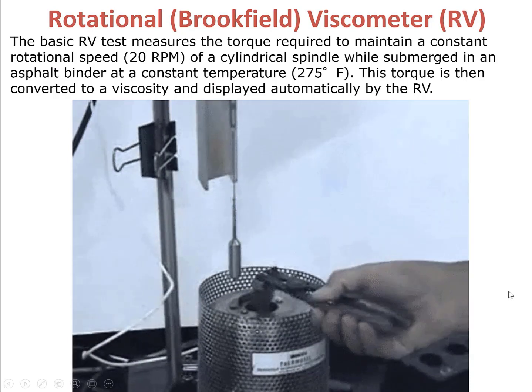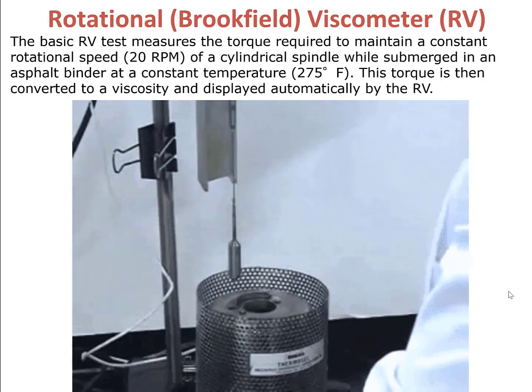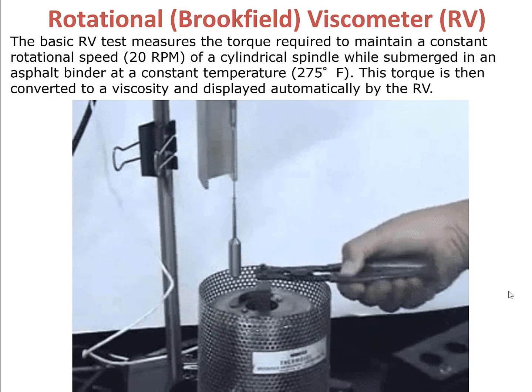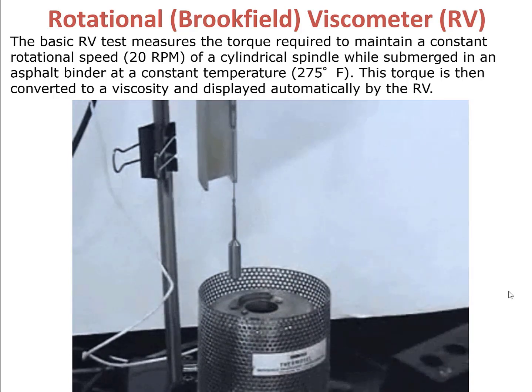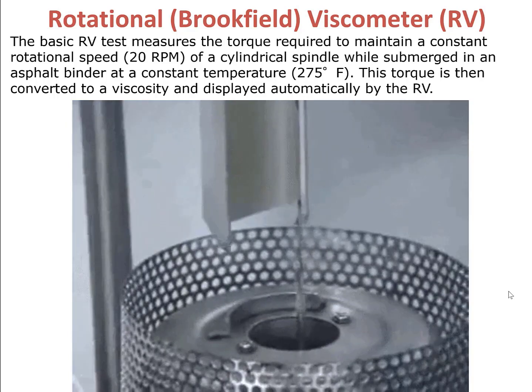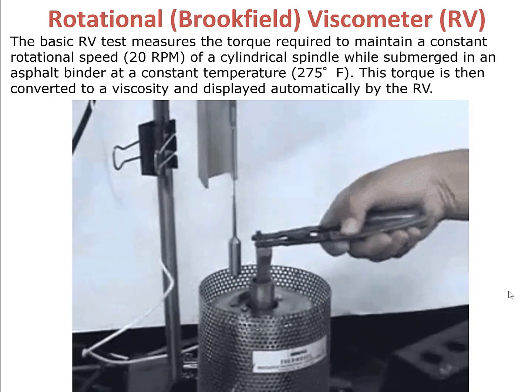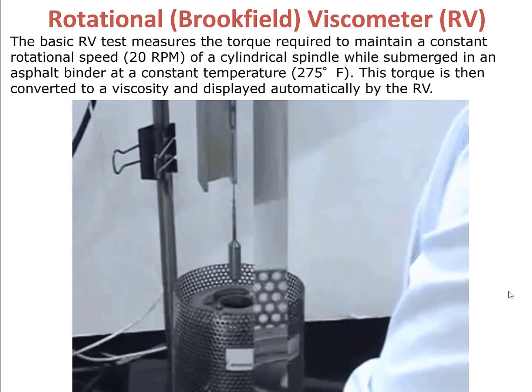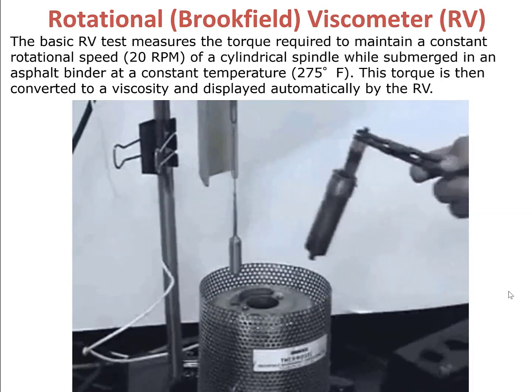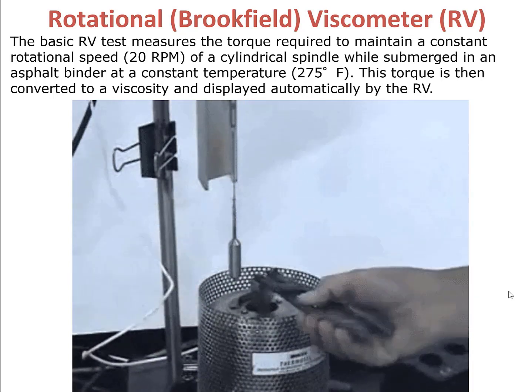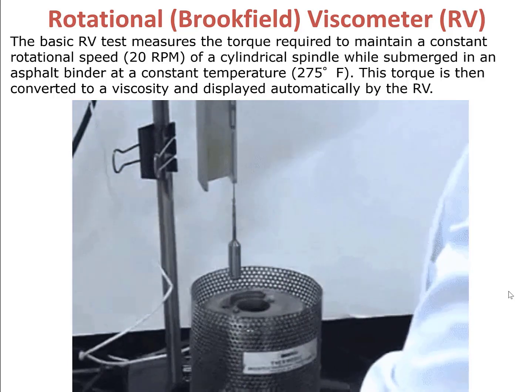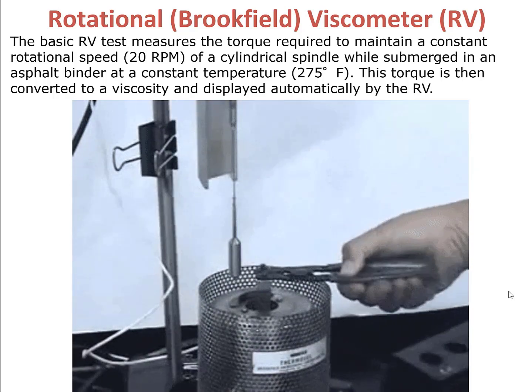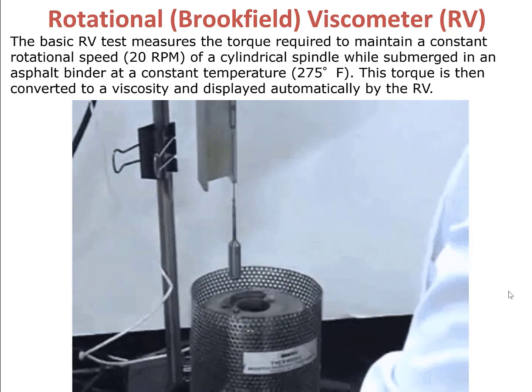We first pour the appropriate amount of asphalt binder into the sample chamber, then insert the sample chamber into the environmental chamber, and carefully lower the spindle into the asphalt binder. The viscometer will measure the torque required to maintain a constant rotational speed of 20 rotations per minute when the spindle is submerged in the asphalt binder at 275 degrees Fahrenheit. This torque is then converted to a viscosity value, which is displayed automatically by the viscometer.